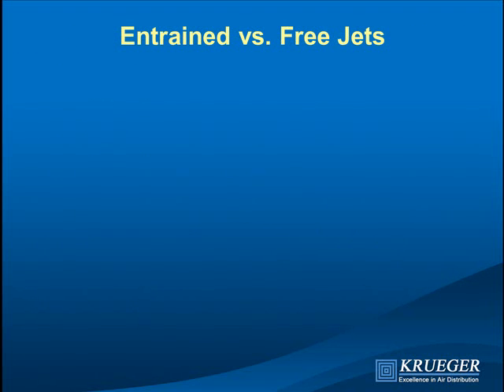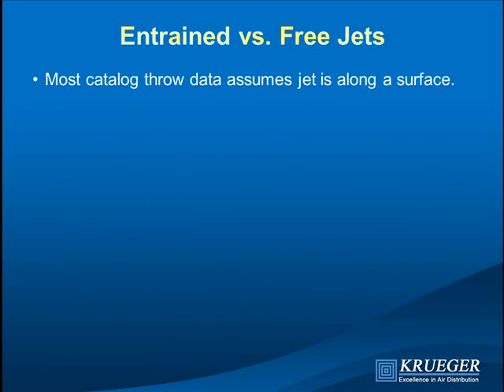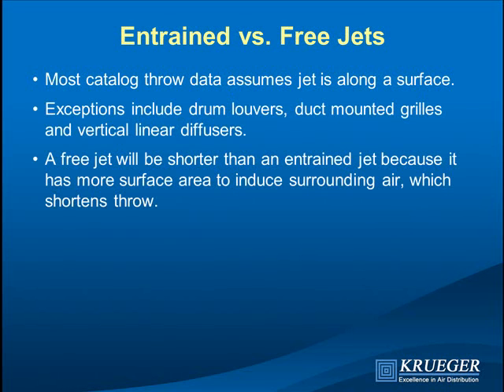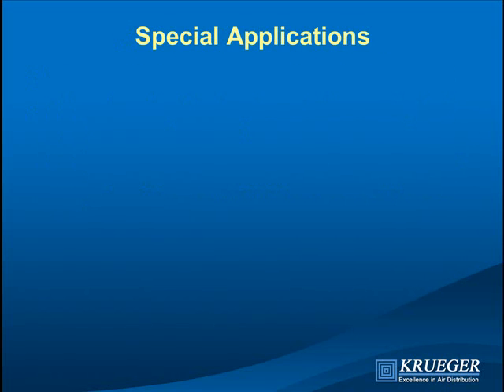Most catalog diffuser data assumes the jet is along a surface. Grill data assumes the grill is within nine inches of the ceiling, so the jet moves along the ceiling and only induces air on one side. Drum louvers, duct-mounted grills, and vertical linear diffusers, however, typically operate as free jets, which can entrain air from both sides. A free jet gains mass faster and therefore slows down sooner. The correction factor is one over the square root of 2 (approximately 0.707) to convert from entrained to free-jet throw.